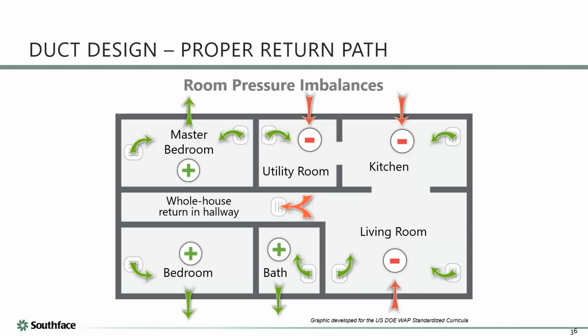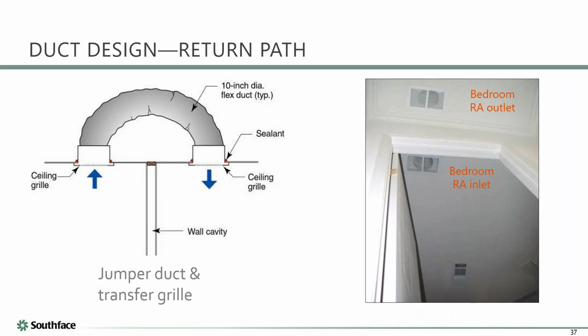But we've also talked about this issue in some other webinars, where we have the main return in the hallway of the house, and all the bedrooms have supplies but no return path. So when we close the bedroom doors, the bedrooms go positive and the main part of the house goes negative. And that can drive infiltration and exfiltration and create comfort issues. So here's a great solution, this jumper duct.